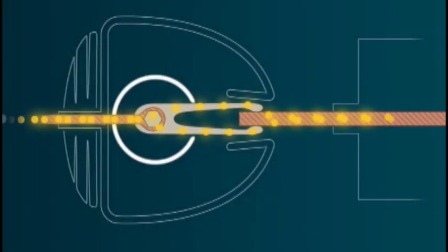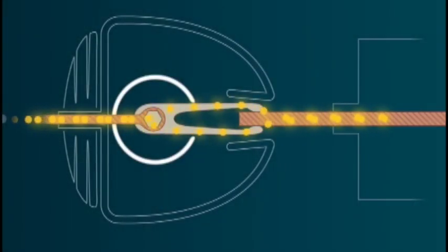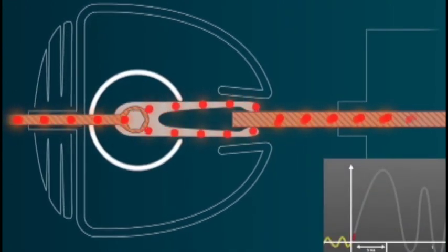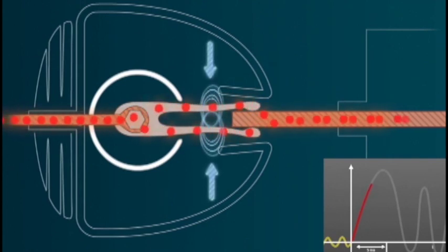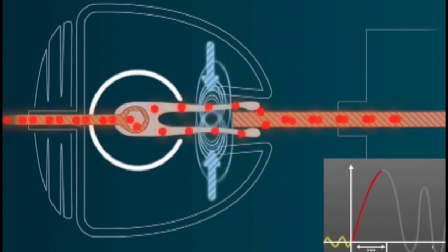The magnetic field between the parallel fingers of a Lyra contact explains why these kind of contacts should be short-circuit safe. Parallel electrical conductors with the same current direction and similar current levels are pressed together, which is the result of magnetic fields overlapping and strengthening. The higher the short circuit current is, the higher the pressure of the contacts should be.